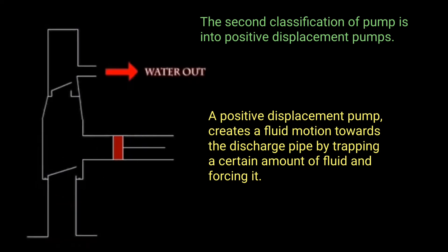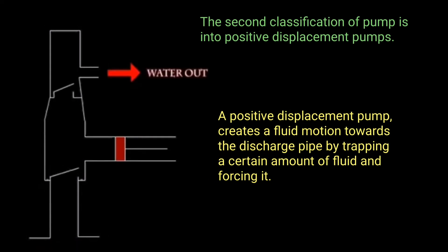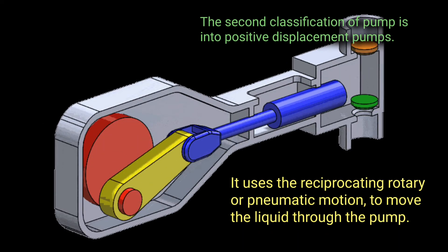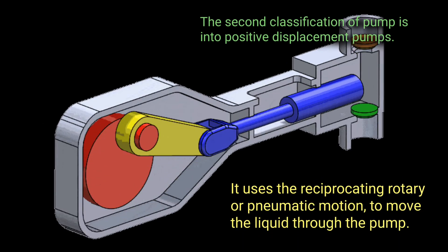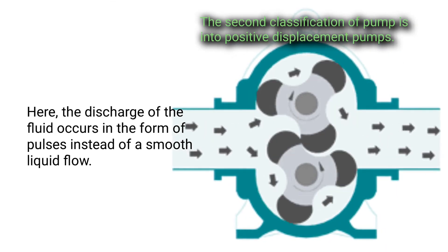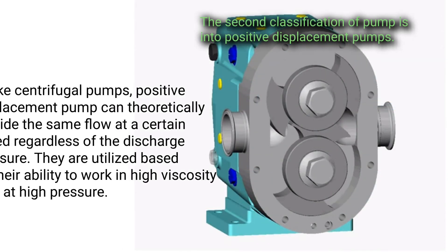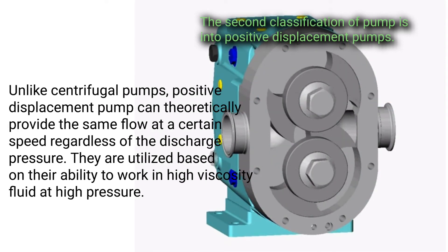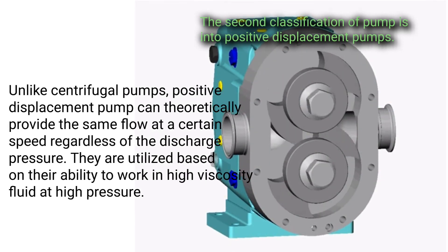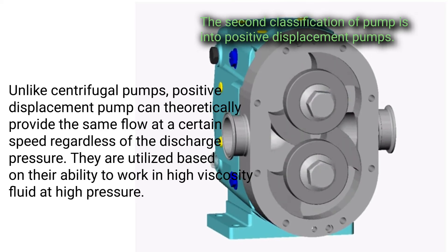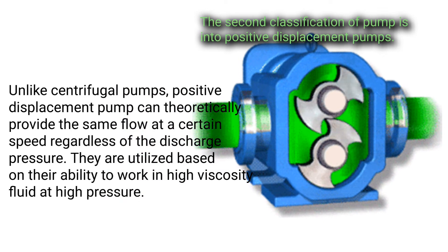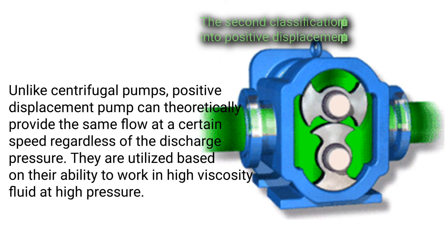The second classification of pumps is positive displacement pumps. A positive displacement pump creates fluid motion towards the discharge pipe by trapping a certain amount of fluid and forcing it out. It uses reciprocating, rotary, or pneumatic motion to move the liquid through the pump. The discharge of fluid occurs in the form of pulses instead of a smooth flow. Unlike centrifugal pumps, positive displacement pumps can theoretically provide the same flow at a given speed regardless of discharge pressure, and are utilized for high viscosity fluids at high pressure.